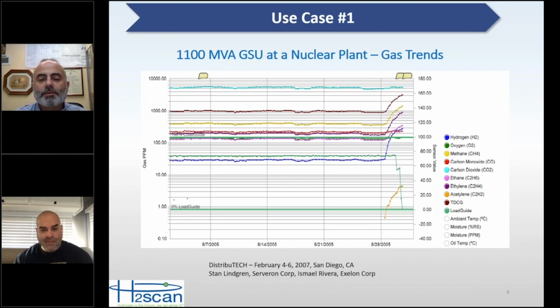So now I'm going to go through a use case. This is actually a very large transformer at 1100 MVA, a generator step-up transformer in a nuclear plant. And this is about a month's worth of data. During most of the month, everything's looking fine, right? You do have some gassing going on in the transformer. This transformer, from what I understand, was less than 2 years old. So to have some of these gases in there, of course, was not a good thing.